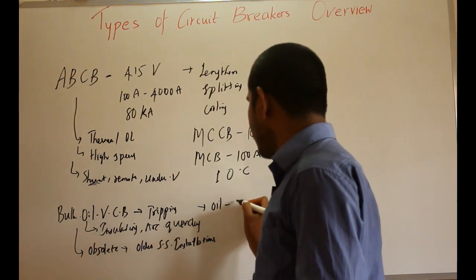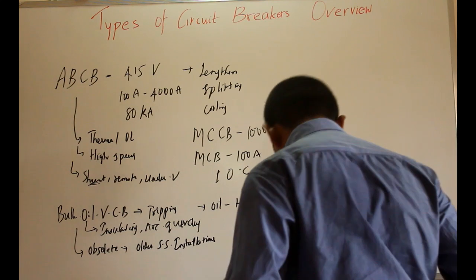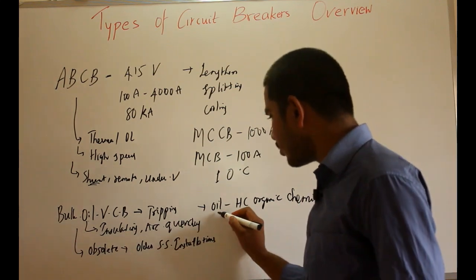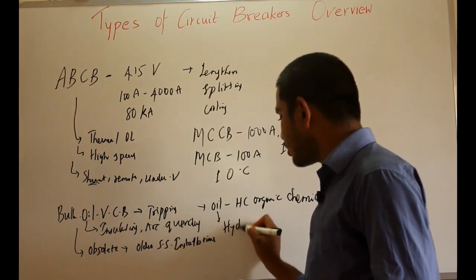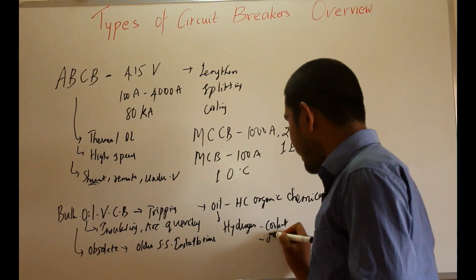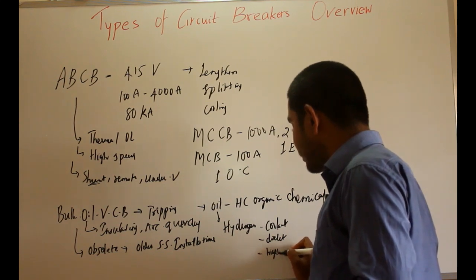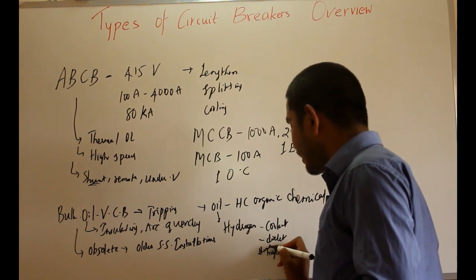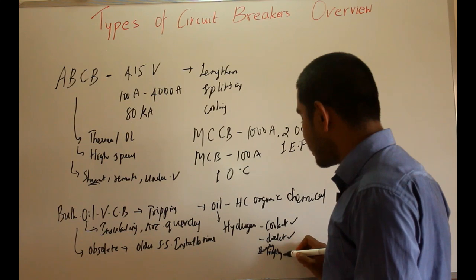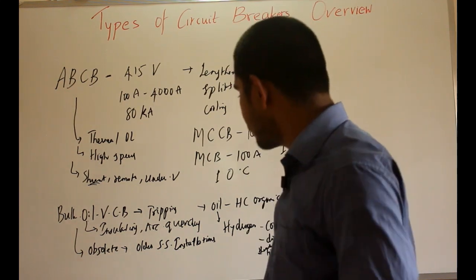The oil is a hydrocarbon organic chemical material. Due to arcing, decomposition of this oil occurs and generates hydrogen. This hydrogen has two important uses: it works as a coolant, it has high dielectric strength, and it is thermally highly conductive — meaning it can conduct heat very effectively. So hydrogen gas can be used to quench the arc, or you can go for self-blast mechanisms.